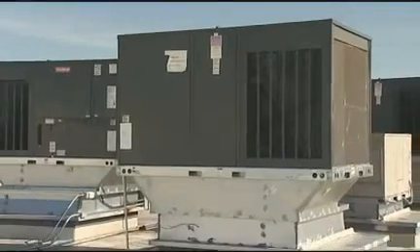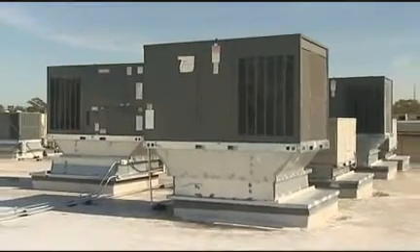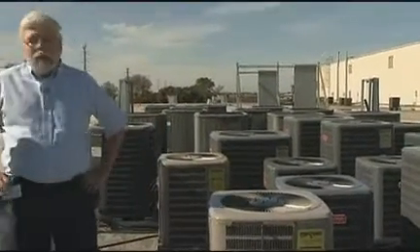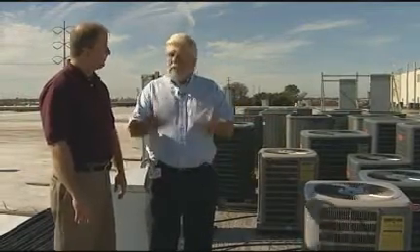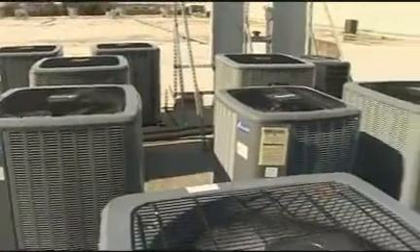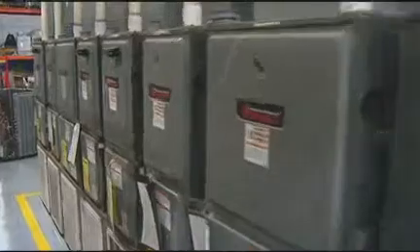We've been inside all day looking at where you do all of the testing. It's all indoors. Do you ever test any of your stuff outside? Well, we certainly do. We've got a farm of units up on the roof of this building, and perhaps that's the next thing I should show you. Sounds great. So Mark, out here you see one of our reliability test farms. What you're looking at here are a bunch of condensing units, and for those who are observant, these are installed too close together. We've done that purposefully so that we can stress the equipment. Some of this product will be operating with dirt that's been injected into it, or with water that's been injected. Those types of stresses, so that if and when the equipment sees that type of environment in the field, we know it's going to stand up over time. I can't overemphasize the commitment we have to making sure that the product is going to last and last and last.